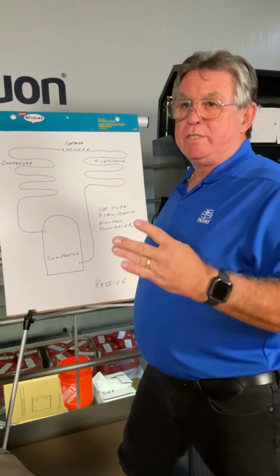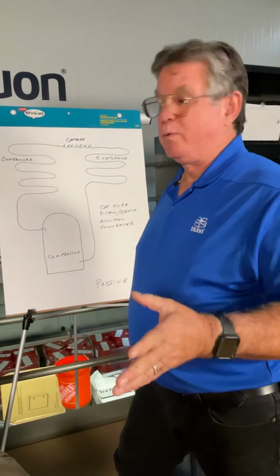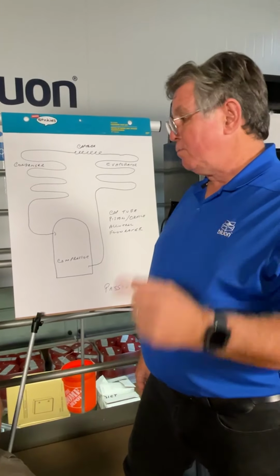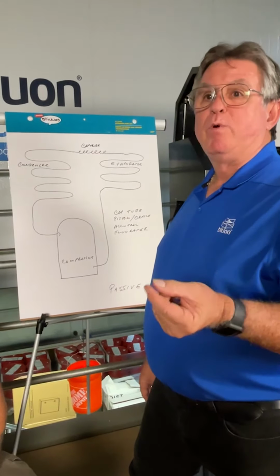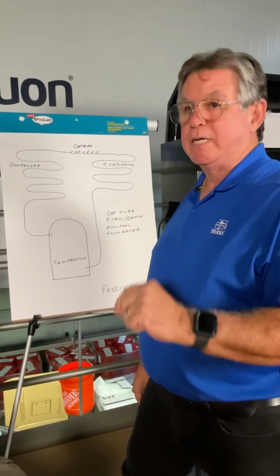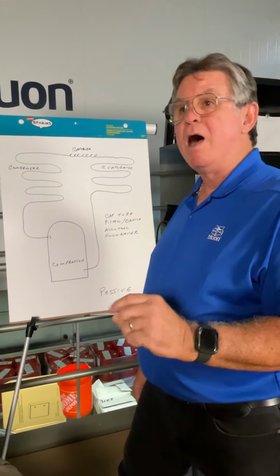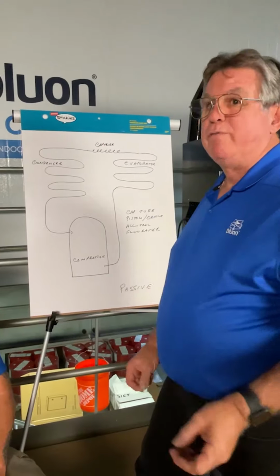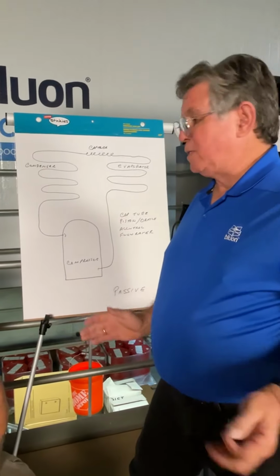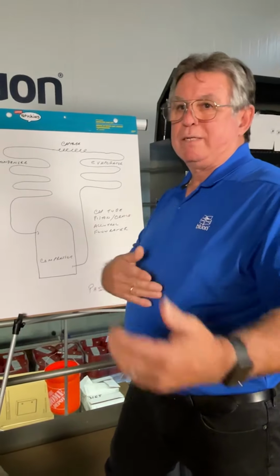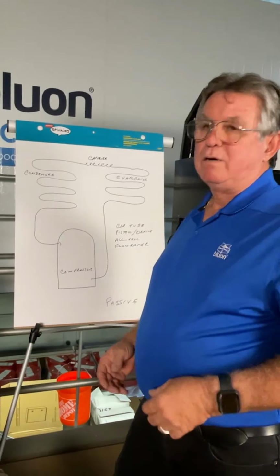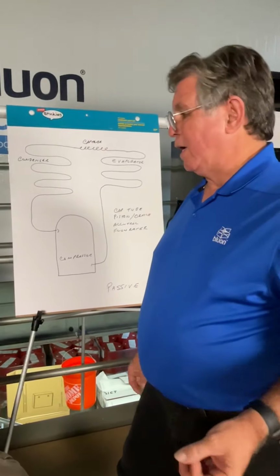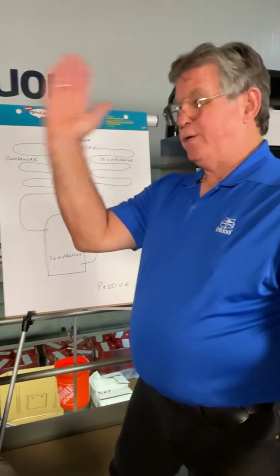So anyway, what Jed, mechanical engineer, did, really, really cool. He's got outdoor dry bulb. He's got return air, and it's supposed to be wet bulb. It says wet bulb, but it's return air dry bulb. And then kind of pick. So if you're down south, grab 60% relative humidity. If you're somewhere around Texas or somewhere like that, go ahead and grab like maybe 40. If you're in Arizona, you're screwed. You got no humidity. But the nice part about the app and our target superheat calculator is you can do it both ways.